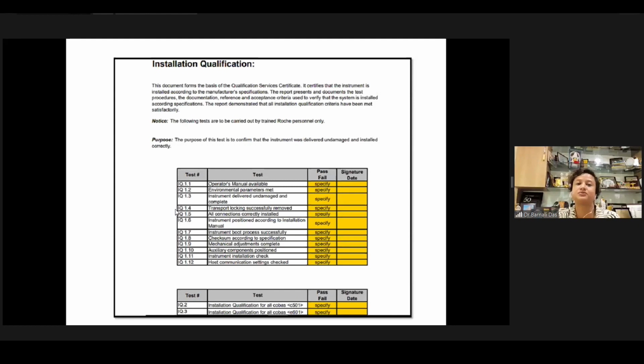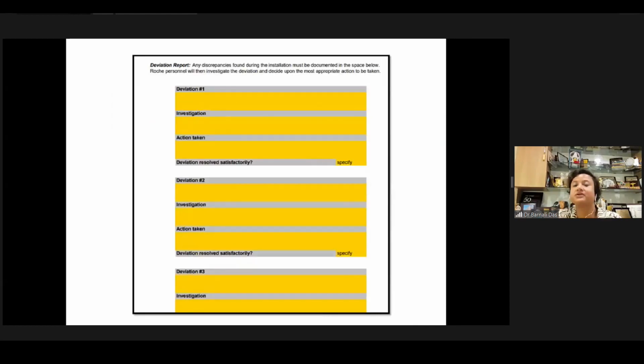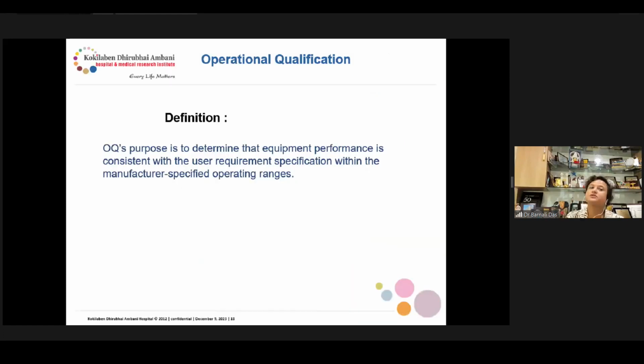If we see the checklist, this is one checklist from our lab. These are the items: operator manuals, environmental parameters, instrument delivered undamaged, transport locking, all connections correctly installed, instrument positioned according to installation manual, instrument boots successfully, then specification met or not, mechanical adjustment, auxiliary components position or not. So these are different components that we should check when we are signing the IQ report, to see that they are installed properly or not. Or if there is a deviation, what corrective action and preventive action the IVD supplier has taken, and whether the deviation was resolved satisfactorily or not. Now coming to the OQ.